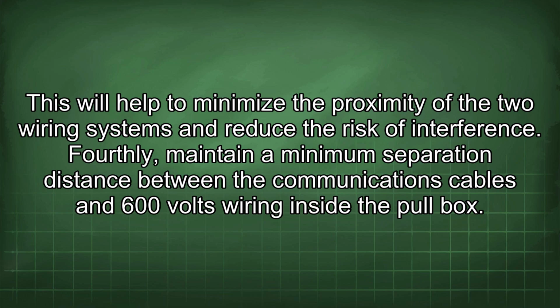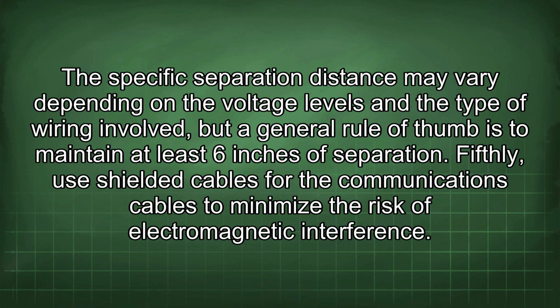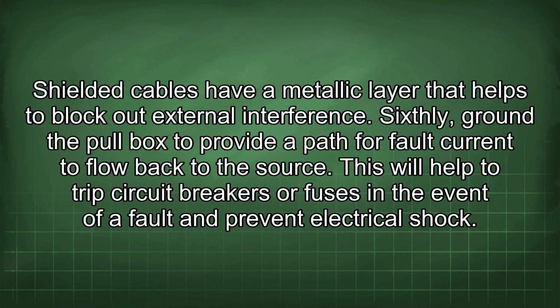Fourthly, maintain a minimum separation distance between the communications cables and 600 volts wiring inside the pull box. The specific separation distance may vary depending on the voltage levels and the type of wiring involved, but a general rule of thumb is to maintain at least 6 inches of separation. Fifthly, use shielded cables for the communications cables to minimize the risk of electromagnetic interference. Shielded cables have a metallic layer that helps to block out external interference.